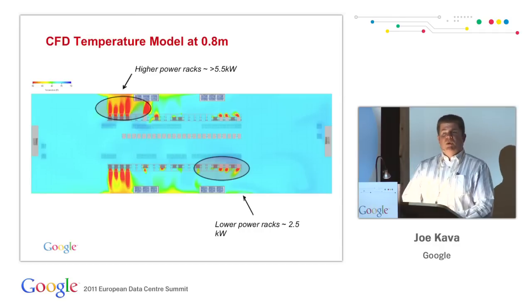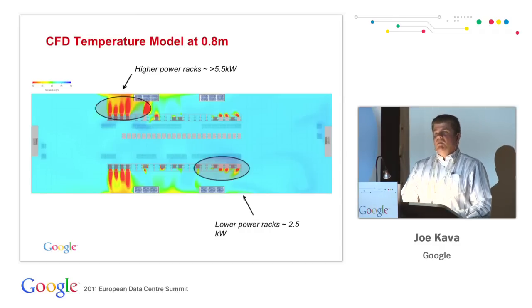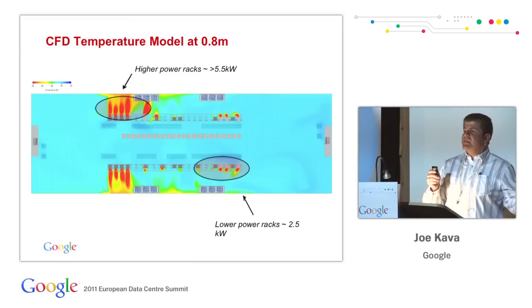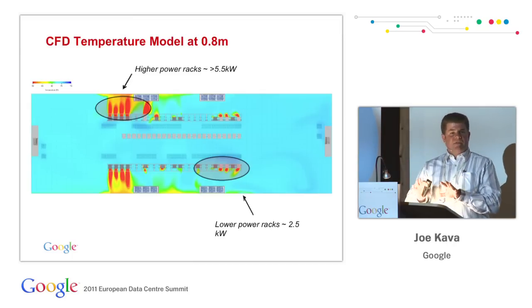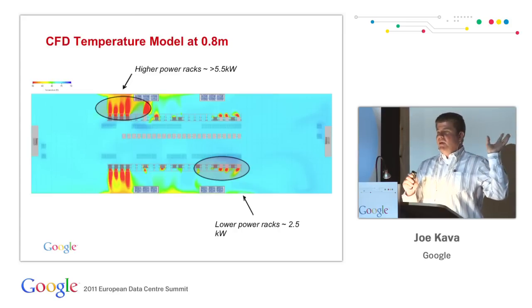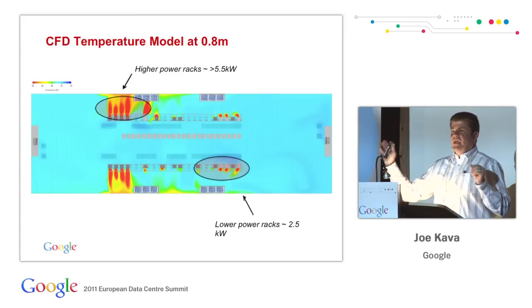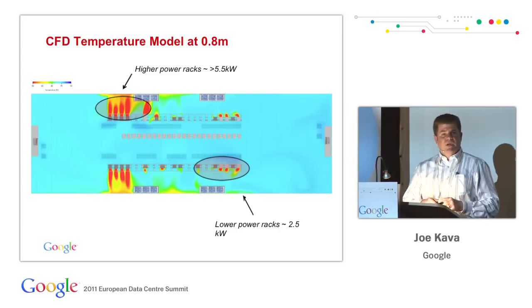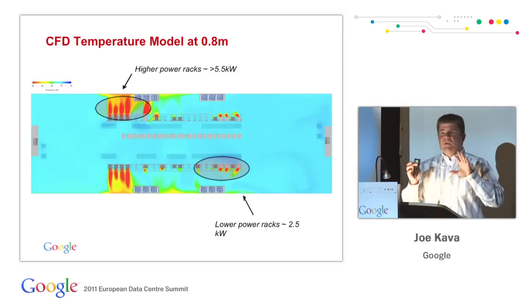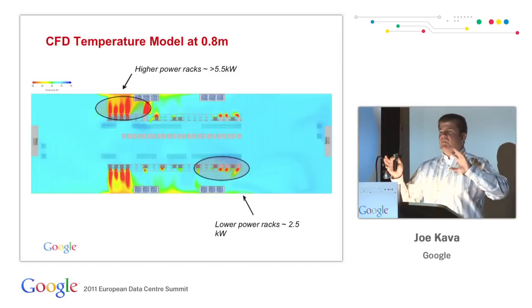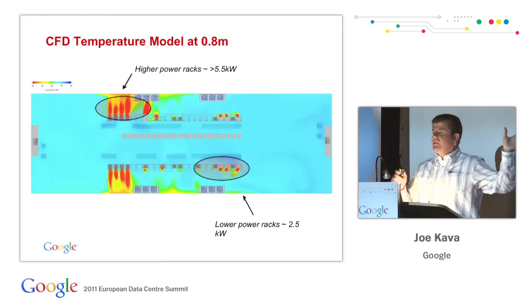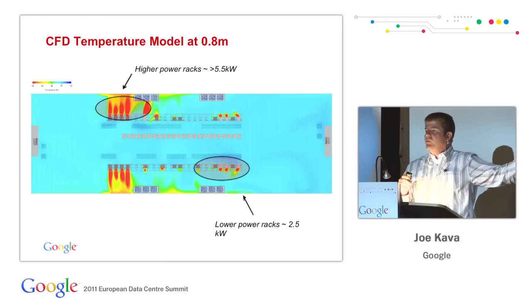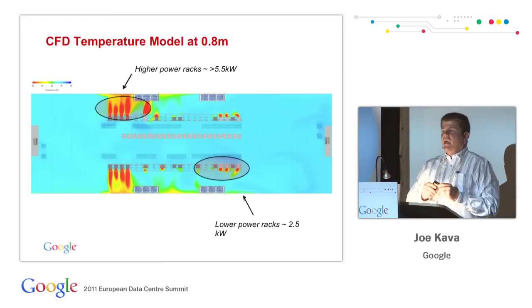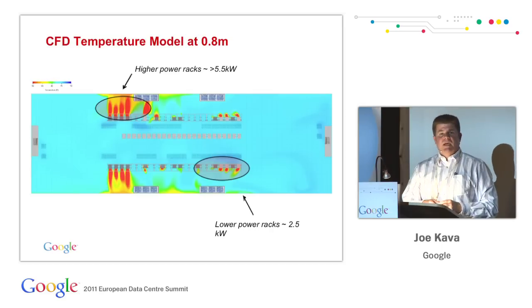We also did some thermal modeling. And as I mentioned, this was set up for mixed deployment, so we had some higher density cabinets and lower density cabinets. And this is not even extreme density stuff. This is very typical, 5.5 kW all the way down to 1 to 2 kW per cabinet. So they were set up, on this picture you'll see that the higher density cabinets were really on one side of the room, on the left side of this picture, and the lower density cabinets were on the right side.